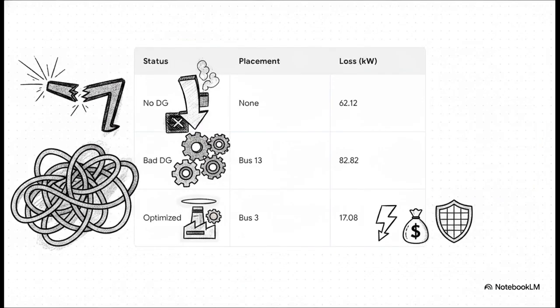So the crucial point is the stark contrast we end up with here. Doing nothing leaves us bleeding 62.12 kilowatts of wasted energy. Guessing wrong and improperly placing a generator spikes our losses to a very dangerous 82.82 kilowatts. But by using evolutionary mathematics to upgrade our infrastructure, we completely optimize the grid. We place a 1 megawatt generator at bus 3, and we slash our losses to just 17.08 kilowatts. It's a massive leap in efficiency. It saves energy, it heavily reduces costs, and it absolutely prevents grid failure.